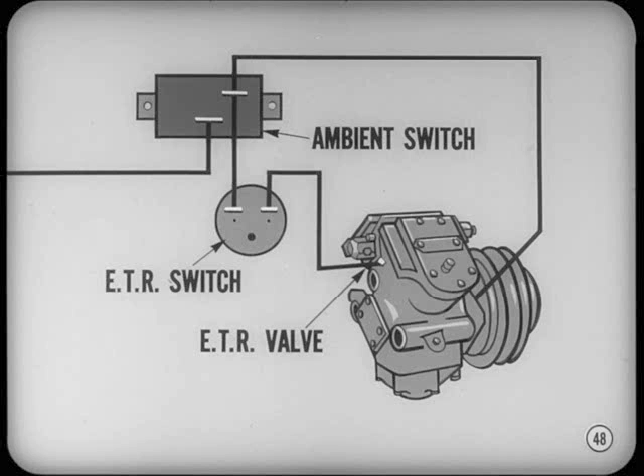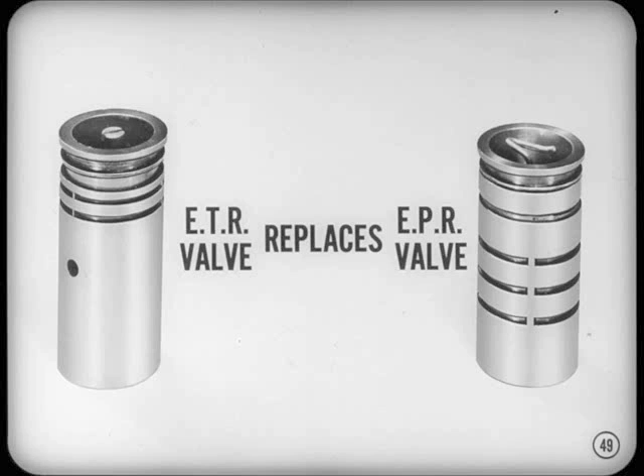The output terminal of the ETR switch is connected to the ETR valve, which is located at the inlet side of the compressor. ETR valve? What happened to the EPR valve? On this Auto-Temp system, the evaporator temperature regulator valve replaces the evaporator pressure regulator valve. They both accomplish the same thing. Control refrigerant flow so the evaporator won't get too cold and frost up.